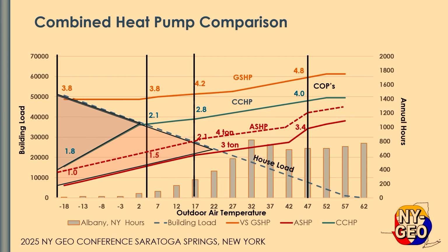And you can see one of the benefits of the ground source heat pump is that once you hit full runtime in this area here, we can actually maintain that very high efficiency of 3.8 all the way through there. And so the result is that there is no auxiliary heat really necessary for the ground source heat pump.